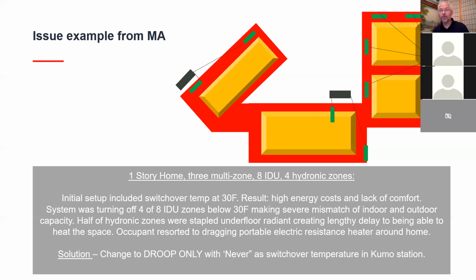And my client, my tenant, was really uncomfortable. So how do you fix this? Well, honestly, the fix was really just going into the settings and changing it so there was no switchover temperature. That would just never run, because the combination of those 3 multi-zones puts out like 95,000 BTUs at 5 degrees Fahrenheit, consistent with what the load of the house is. It was sized to 100%. And so the frequency that the boiler will need to come on going forward will be basically never.